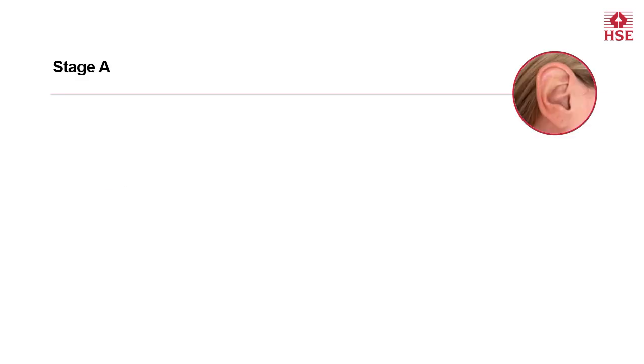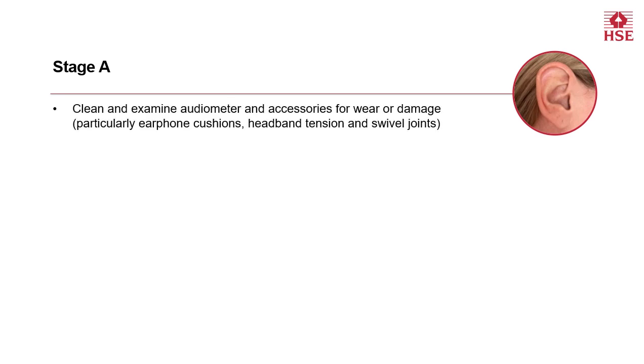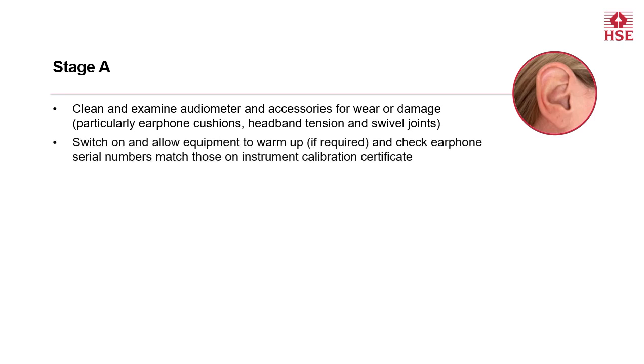The Stage A checks are the most relevant for audiometricians. For these, the only specialist equipment you need are your ears and your eyes. These checks involve cleaning and examining the audiometer and accessories for wear and damage. The earphones are the one piece of equipment that are most likely to be abused, and it is crucial that these are well maintained to ensure that your test results are valid. The earphone cushions, headband tension and swivel joints are particularly prone to wear and damage. The next step is to switch on the equipment and check the serial numbers are what they should be. Earphones and audiometers are calibrated together and should not be swapped around.